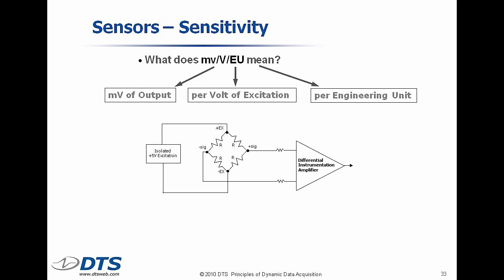So simply put, I have an excitation source here, I have a sensor, and I have an amplifier. So sensitivity means the millivolts of output from the sensor per volt of excitation applied per the physical stimulus applied. And that's what we have to do. We have to get it into that format.